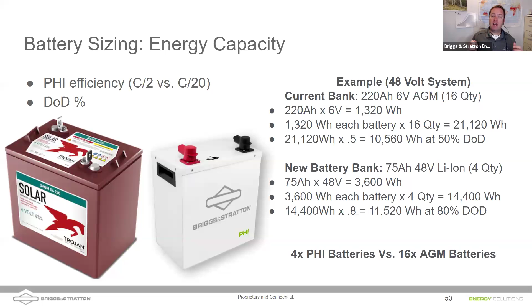Each battery has 3.6 kilowatt hours, times 4, that's 14,000 watt hours. At an 80% depth of discharge, we get about 11 kilowatt hours of usable battery capacity. So you could take out 16 batteries and put in 4, and in that last example we showed 5.